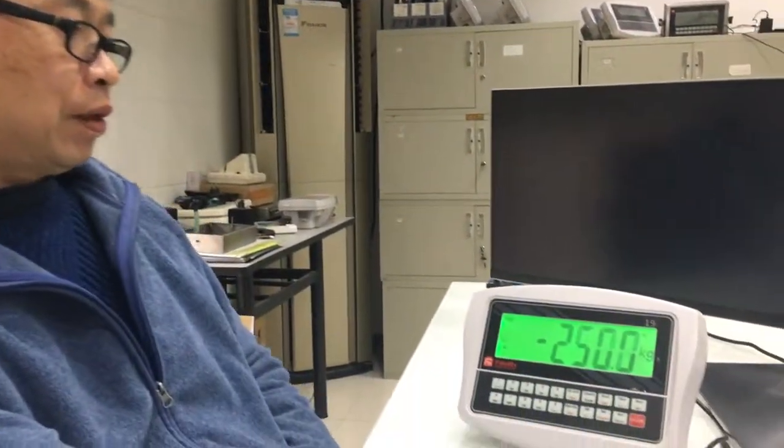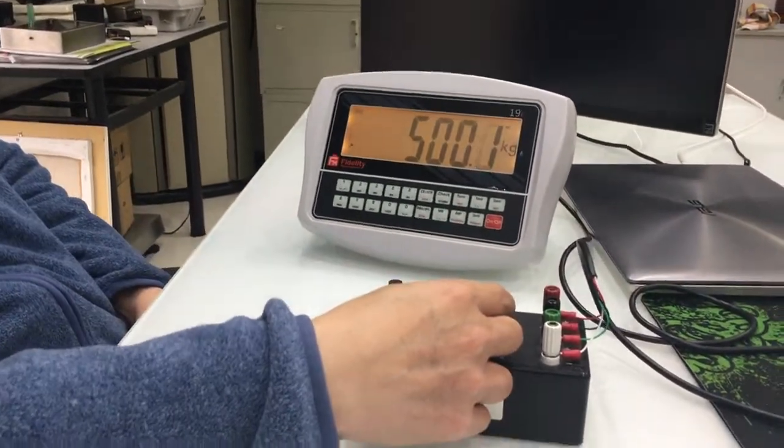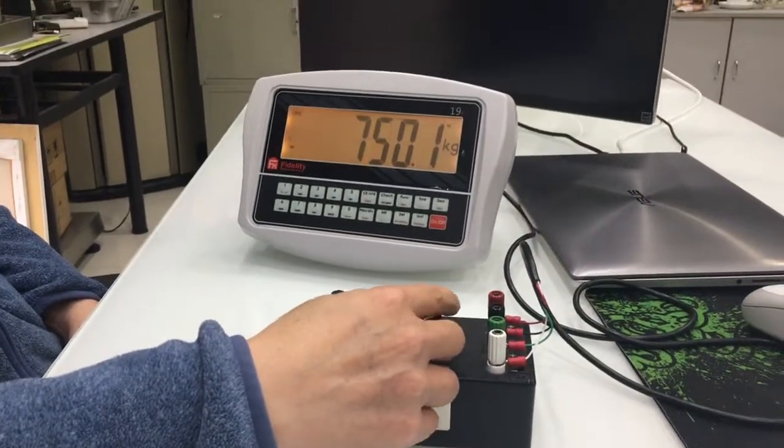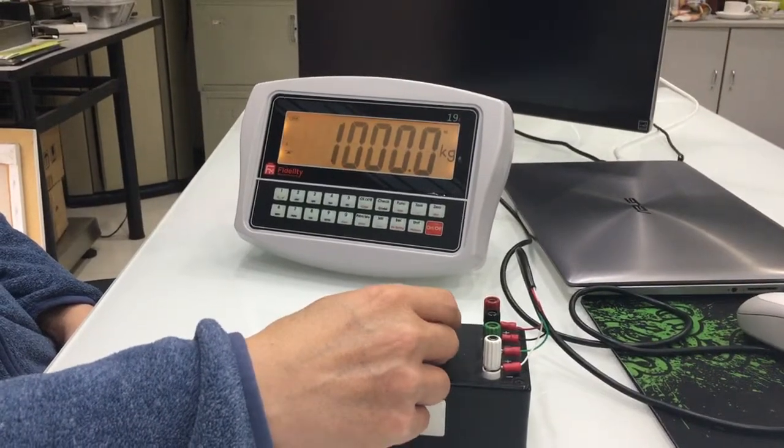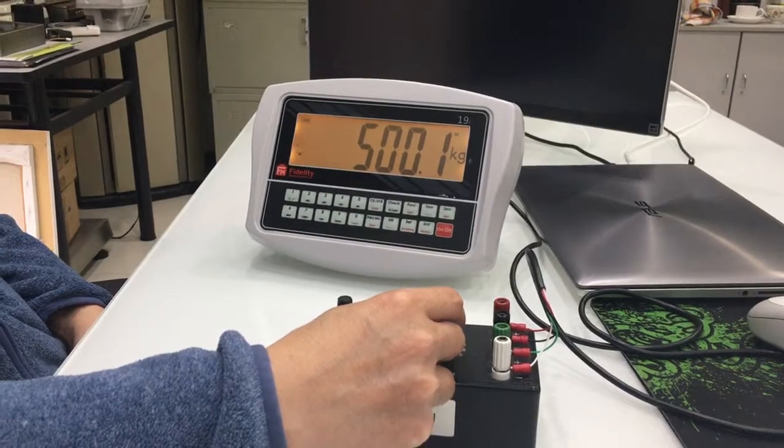Let's take a look first. My target is to set each simulator step equal to 100 kilograms, so the calibration is not correct now.